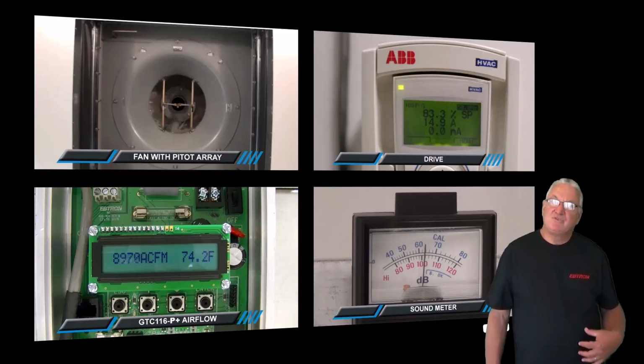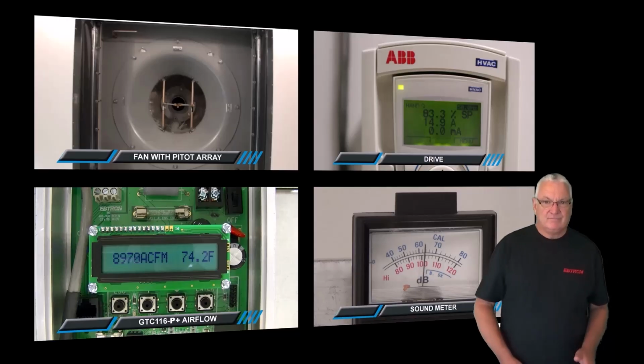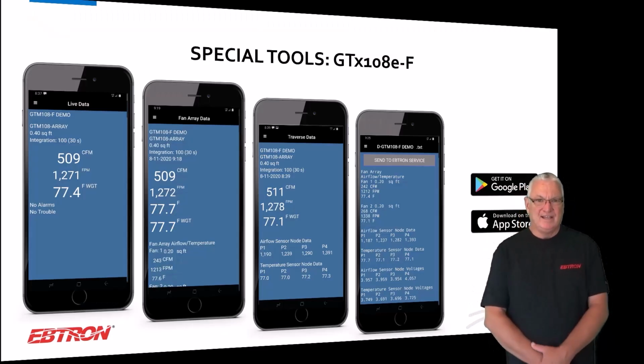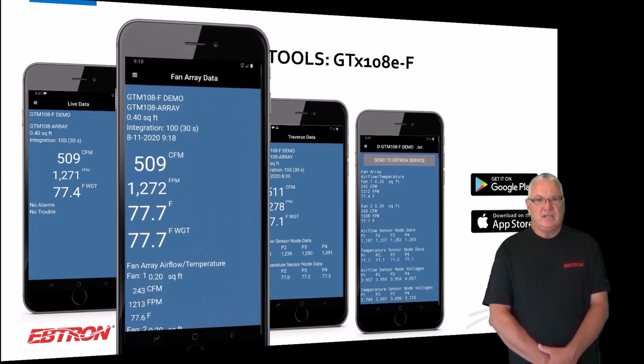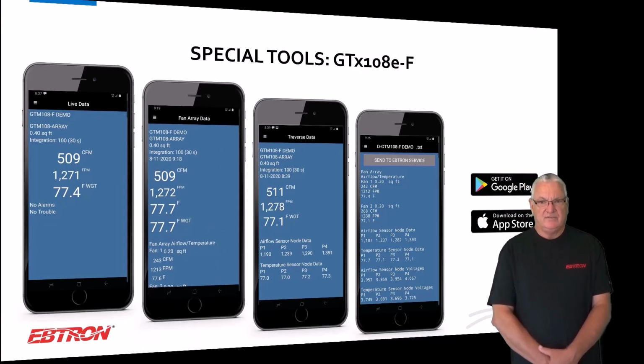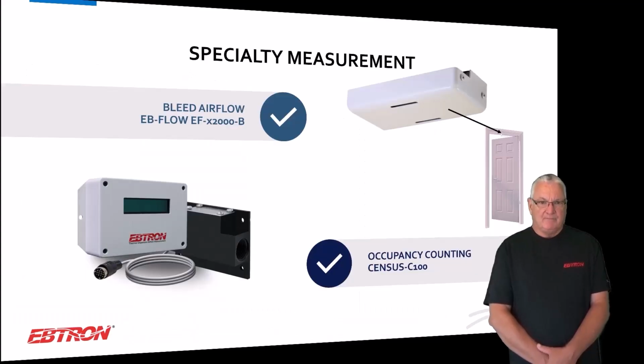We could have put an EBTRON that goes in the throat there. It would have similar result actually. You know, the current has gone significantly higher, the flow has gone significantly lower, and the sound has gone significantly higher. Okay, but that's not what we're doing. When you get to fan arrays, the EBLink has an additional screen which will show you the individual flows of each individual fan. We have some specialty measurement devices outside the scope of today.